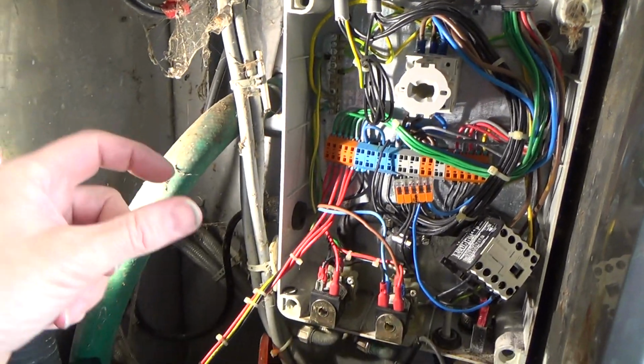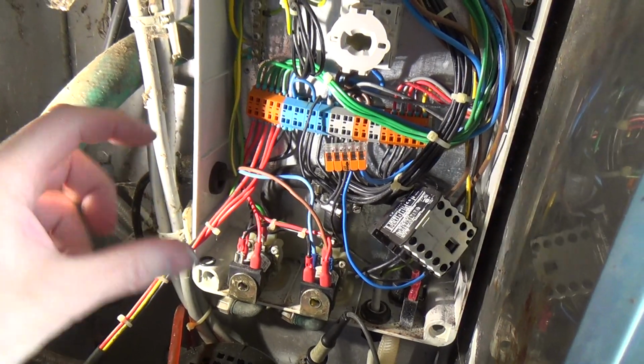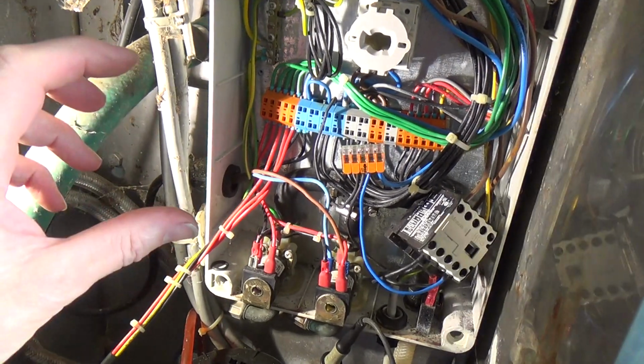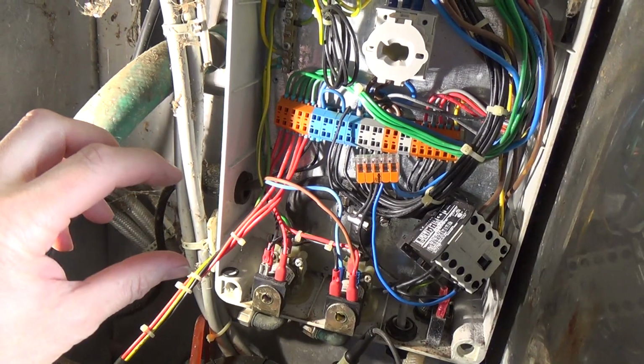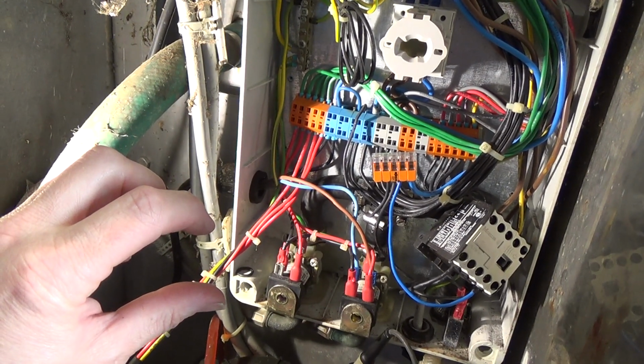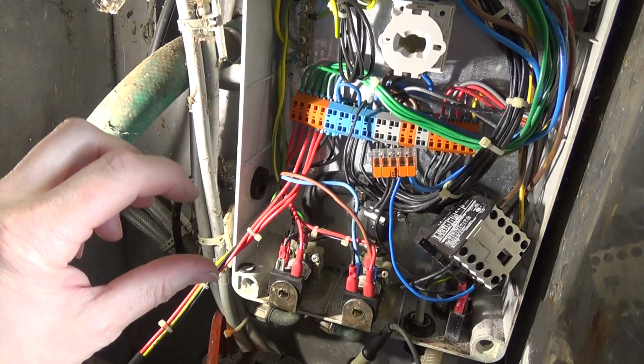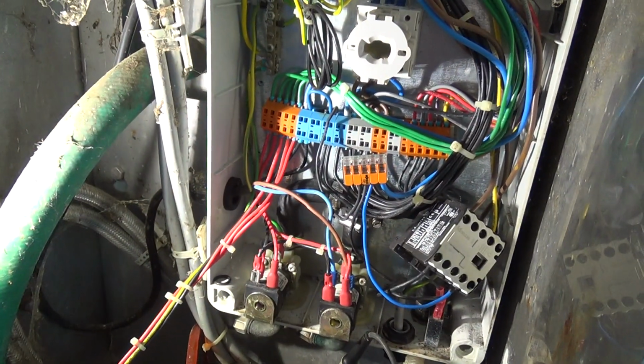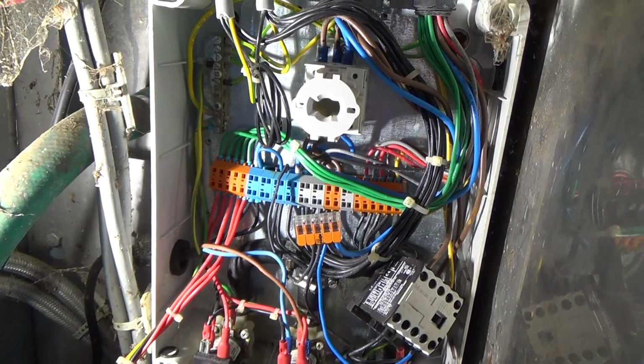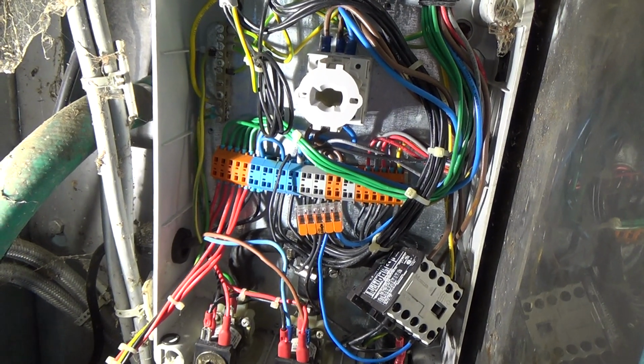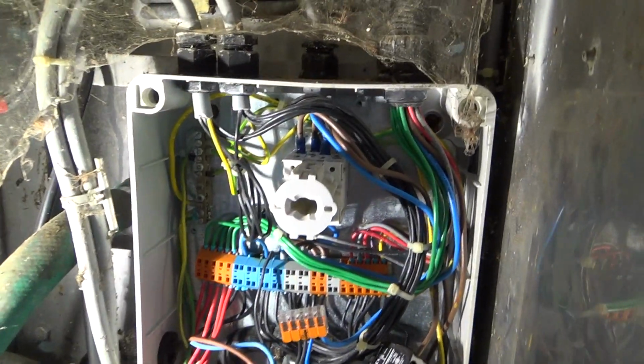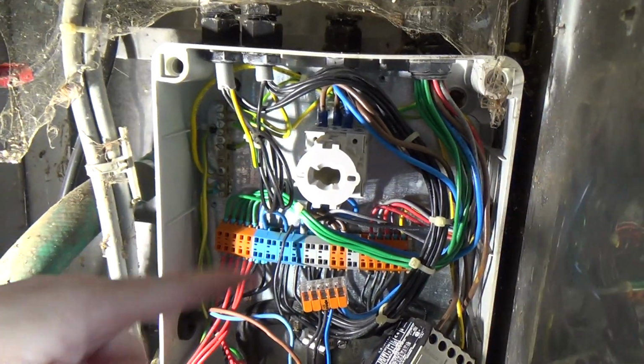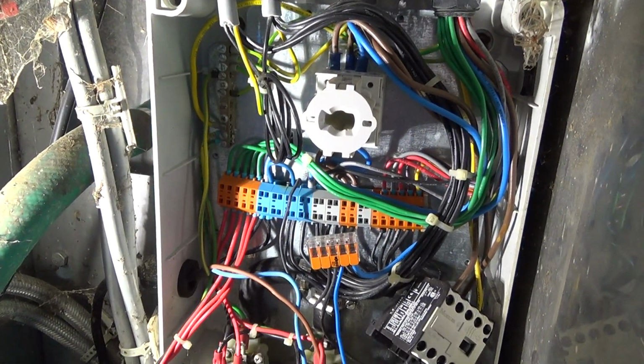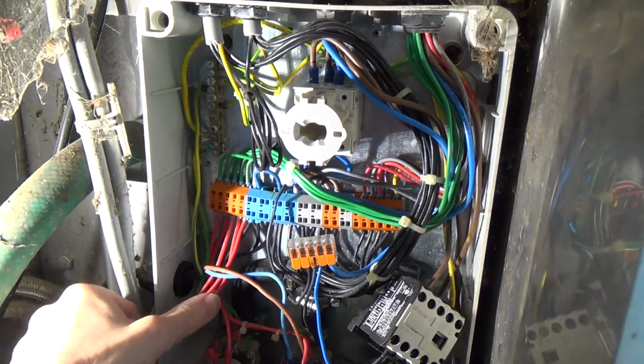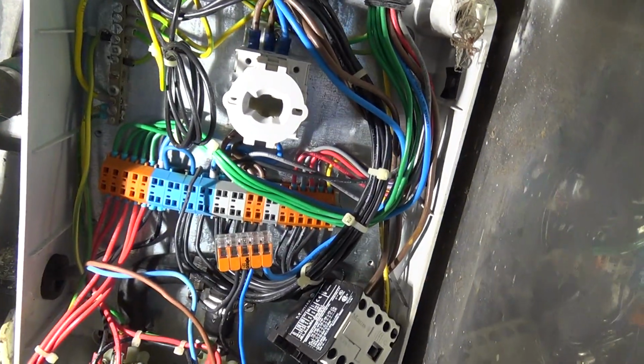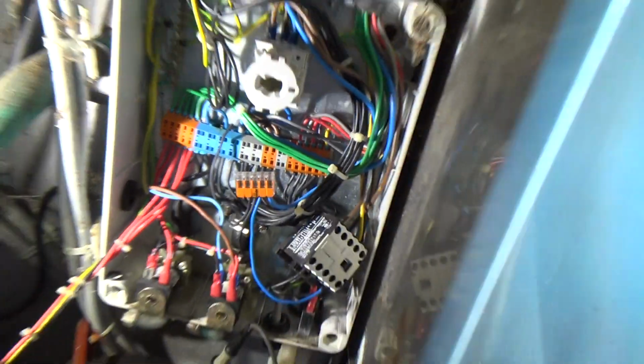Because even knocking the breaker off in the mains board isn't going to do anything, because all the breaker turns off generally is your live, unless it's an RCBO, which is like a little mini RCD and a breaker in one. It's not going to turn the neutral off. Which is why you want a proper 4-pole switch if you've got 3-phase stuff, or 2-pole if you're on single. You really need to be switching your neutrals as well, especially on farm stuff. Anyway, enough wittering.